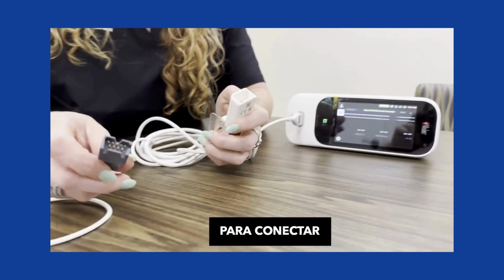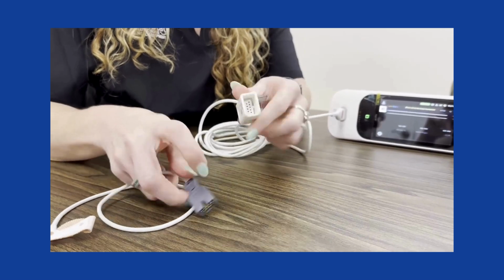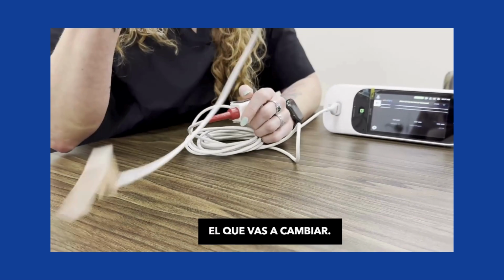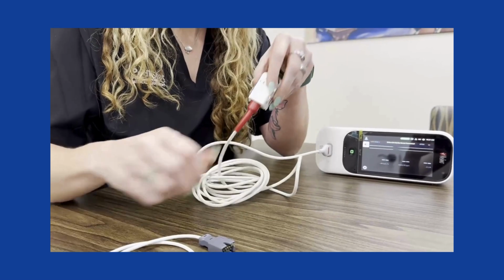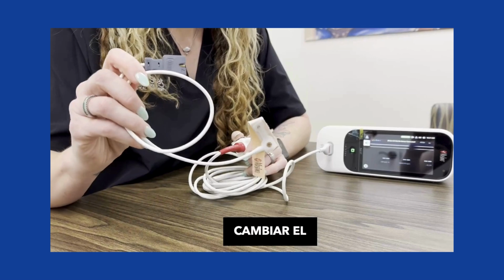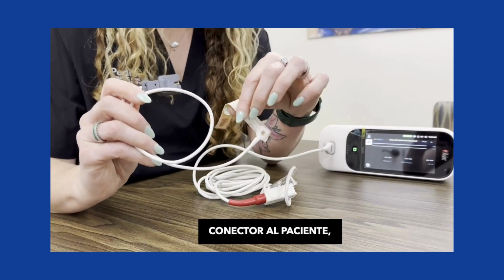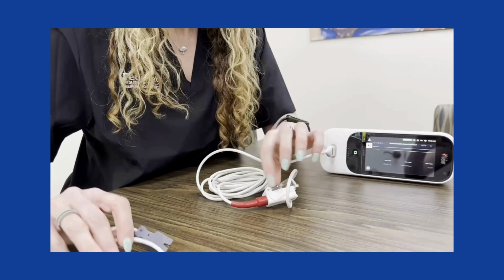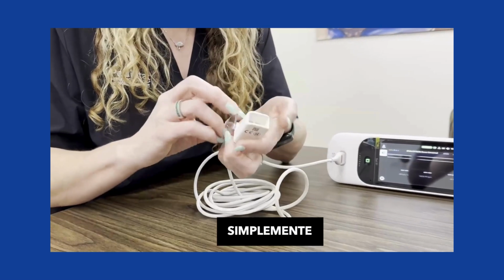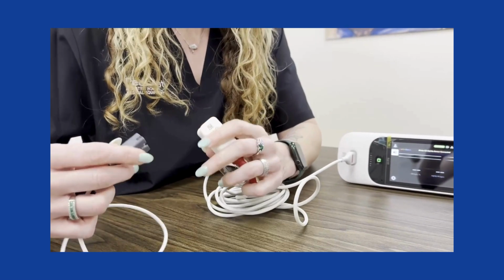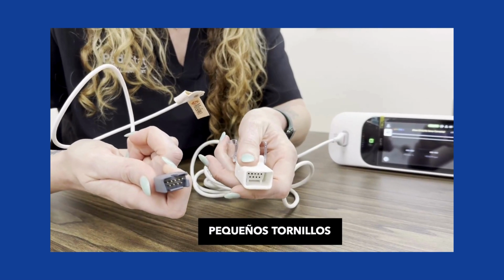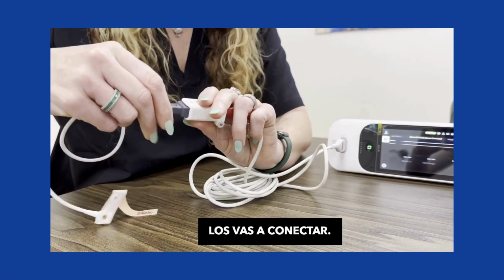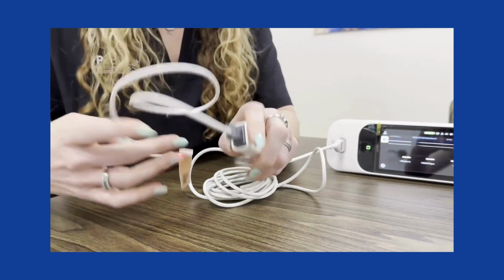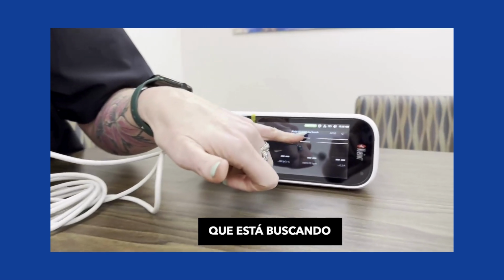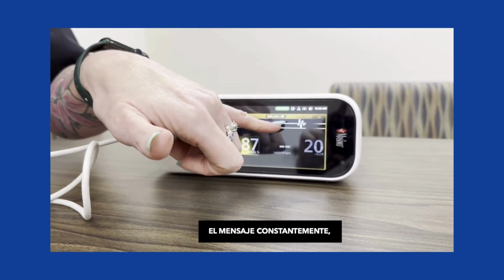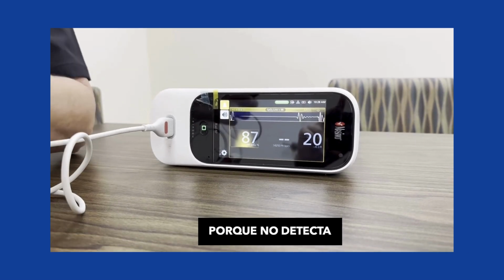So in order to connect this piece, you'll see this part opens, it clips, all right, because this is the one you're going to be switching out. This is permanent, all right? And then when you need to switch out the actual connector to the patient, the disposable, you're going to have to plug it into here. So you just clip this back, all right? You'll see that it has little metal screws there. You're going to connect them. And then it's going to tell you, now it's looking for a pulse. So you see how the verbiage constantly changes, and it's going to start alarming because it doesn't detect a pulse.